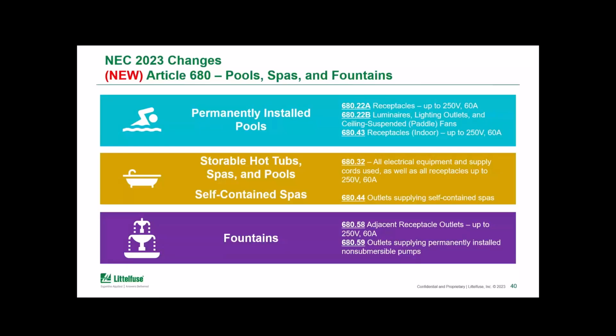And second, Article 680 in the NEC is where there are other changes relative to special purpose GFCIs. This article deals with all the electrical wiring and equipment for swimming pools, fountains, hot tubs, spas, both permanently installed or storable. And it also applies to metallic auxiliary equipment, the pumps, the filters, and the like. So it is quite obvious that these are wet areas which have a high risk of fatal shock if there's any equipment degradation, any malfunction, any improper water ingress, or other damage.